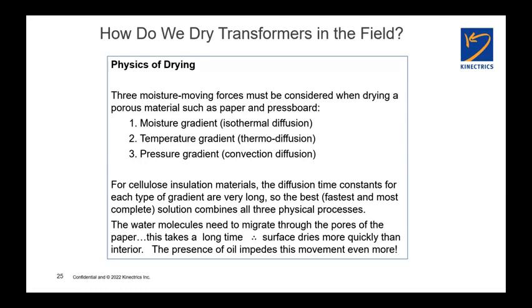I'm not going to get into this other than to say, to remove moisture from cellulose paper, you need three things. You need a moisture gradient, a drier area and a wetter area. You can't just magically poof all the moisture out. You can only pull moisture from a wetter area into a drier area in the bulk of the paper. You need a temperature gradient, i.e. heat, and you need a pressure gradient, or conversely, a vacuum gradient.